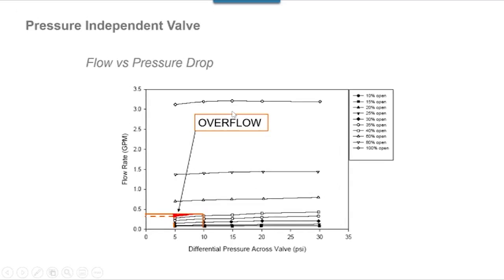Now, the same test was run, but with the pressure-independent control valve. And look again at the overflow area. And keep in mind, we're using different scales for the flow rate, but that overflow is very slight. And again, as you look at this drawing, you notice that the lines are not perfectly straight. There is some variation. Every pressure-independent valve manufacturer that I know of states their accuracy as plus or minus 5% due to system pressure fluctuations. You look at these lines, and that's certainly the case.